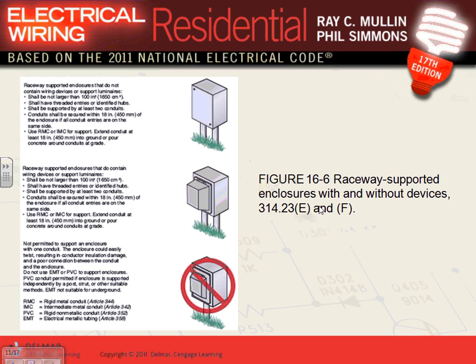And if it doesn't have equipment, probably rigid conduit, IMC or PVC can get you the support. But what they don't want you to do is to support the box from one conduit like this, because it could twist and so forth. So this is what it's saying: if you are to design a system where you want to support the box directly from a conduit, you're looking at rigid or intermediate conduits.